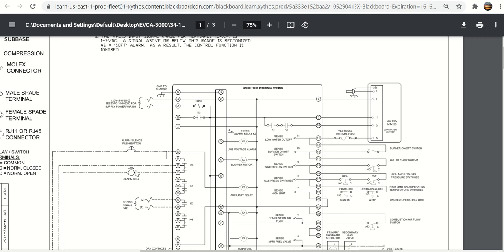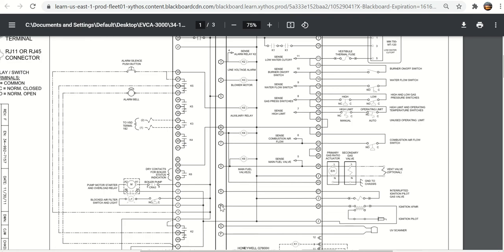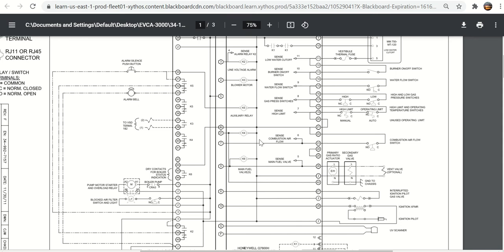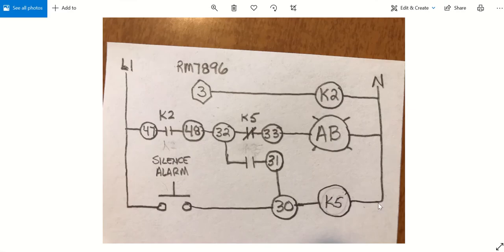When this relay energizes, it turns on this bell. But you want to have the ability for somebody standing outside or standing next to the boiler to push a silence button. That silence button does not reset the flame safeguard, does not make the boiler restart. It only silences the alarm bell. The only way you're going to reset the flame safeguard is to actually open up the panel and get to the reset button that's physically on the front of the flame safeguard. This is kind of confusing how K2 and K5 and silence button and the alarm bell are all laid out. So I made a little sketch and hopefully this makes sense because I'm going to ask questions about this.